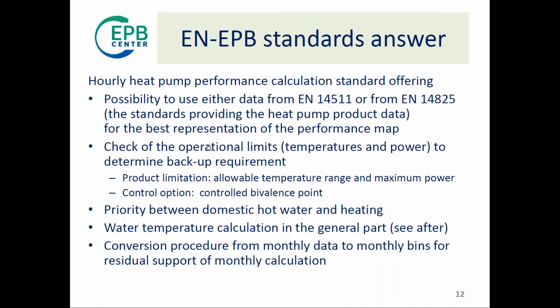Then you have to check the operational limits, temperatures and power, to determine backup requirements. And you might have product limitations. Of course, the heat pump has an allowable temperature range and maximum power. Or it might be a control option: you prefer using another generator when the COP of the pump is not so interesting because of the operating condition at that time. So you have to handle priority between domestic hot water and heating and calculate the water temperature, because without this precise information about operating condition, you might go off the goal with the calculation.